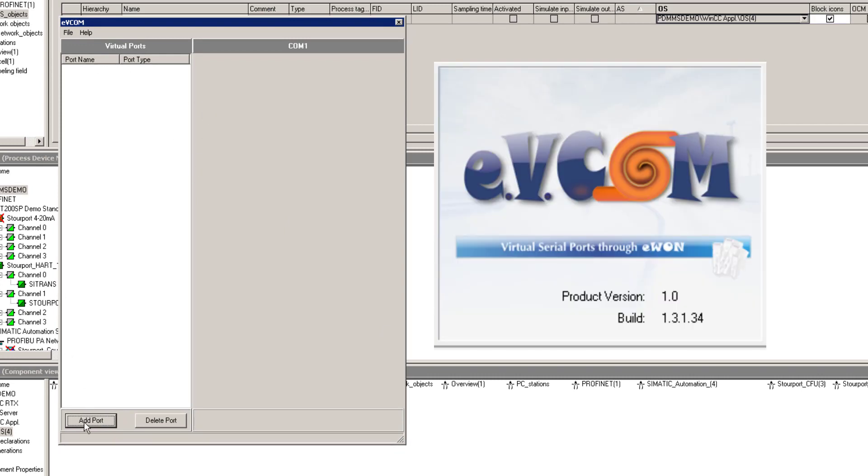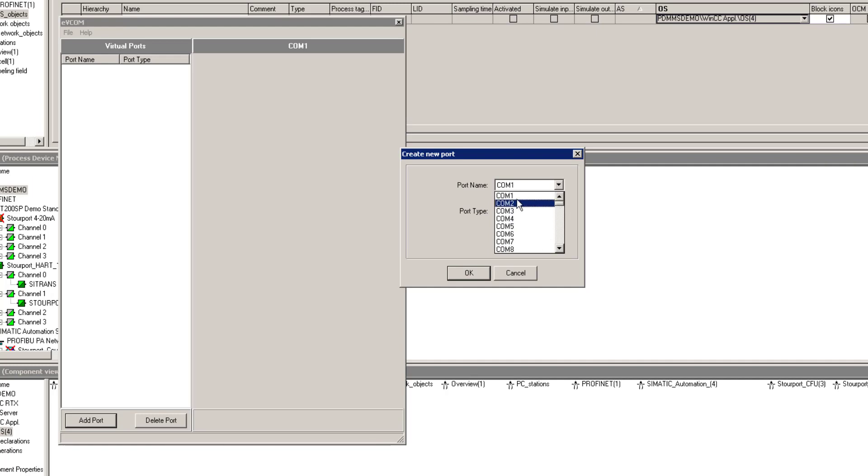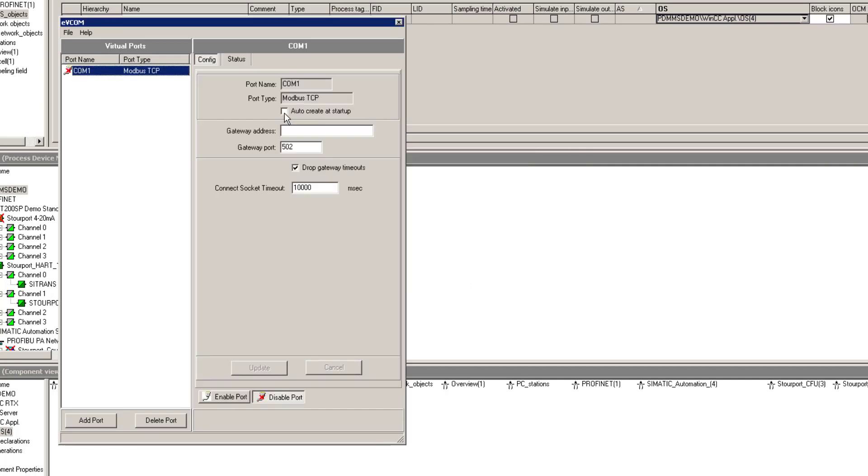So basically add a port. This is going to be your virtual serial port. I have no other COM ports on here. Just be careful that you don't duplicate a port that's already being used. One of the things that tends to use a lot of ports is your Bluetooth interface. So just be careful with that. I'm selecting COM port 1. We can have auto create at startup. This is the IP address of the gateway. You can see there the port gateway 502. So if I've changed it on that gateway, here it would have to match. But I'm keeping it at the default value.